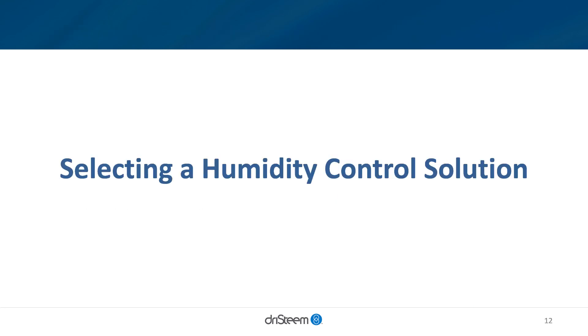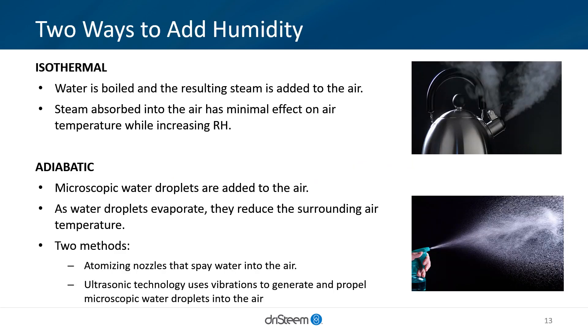Now that you know about the importance of humidity control, we will discuss the various humidity control solutions on the market today. When you need to increase the RH, you can choose between two different humidifier technologies. The first and most common is isothermal humidification. Isothermal humidifiers boil water to create steam, and the water vapor from the steam is then dispersed into the air. When steam is absorbed into the air, it has a minimal effect on air temperature. Isothermal humidification can achieve tight RH control, especially when indoor air temperatures are tightly controlled.